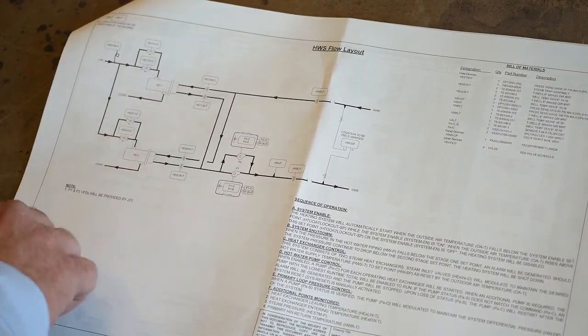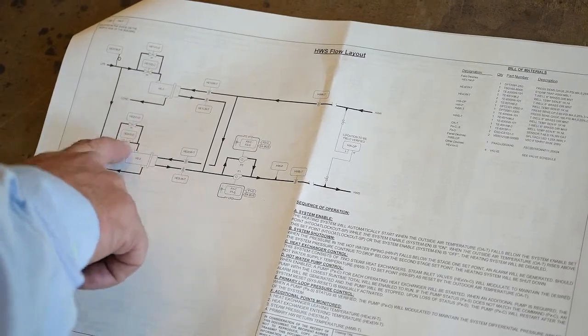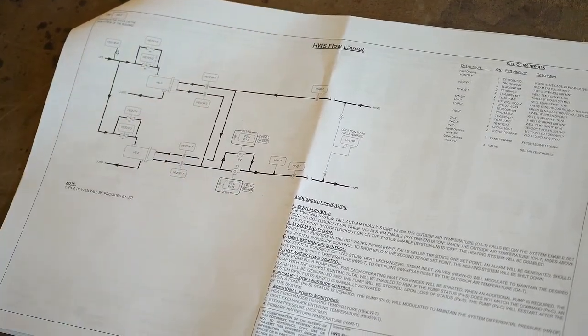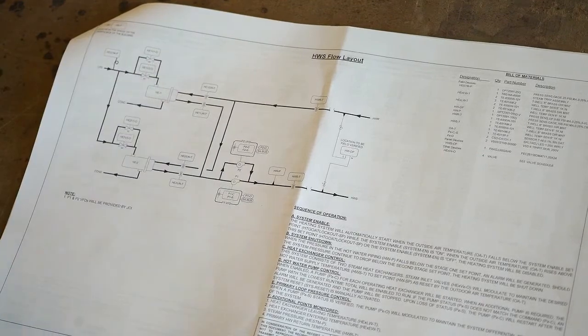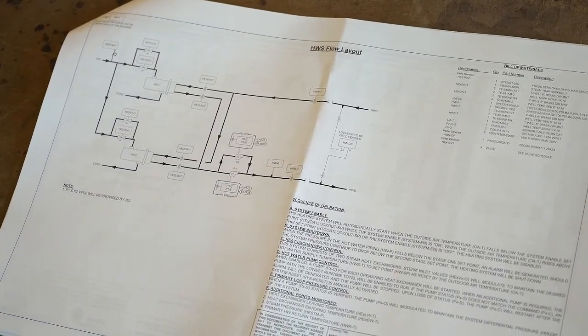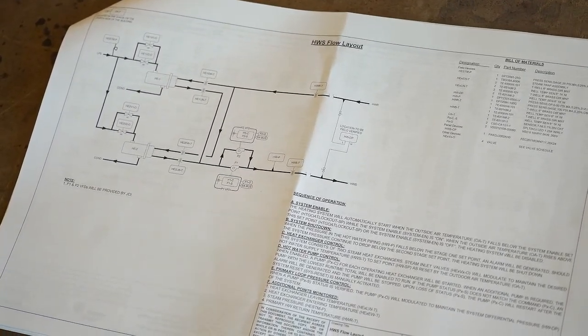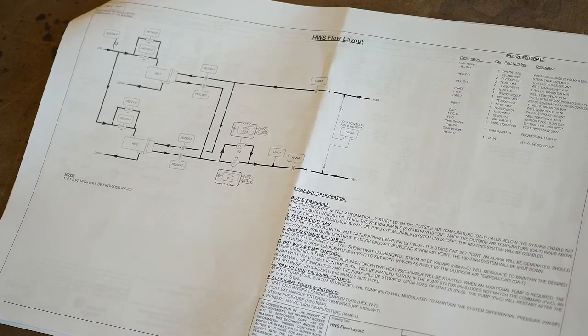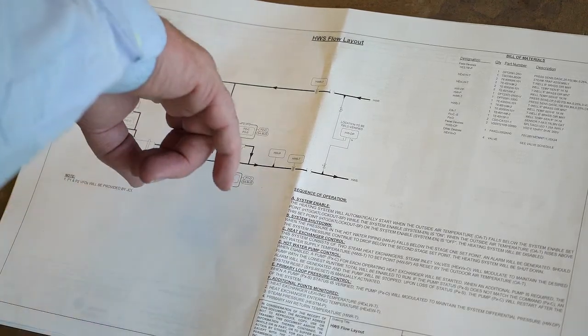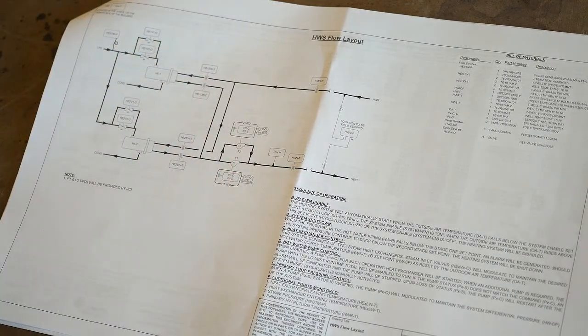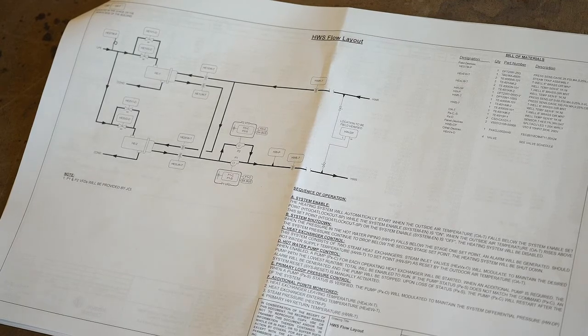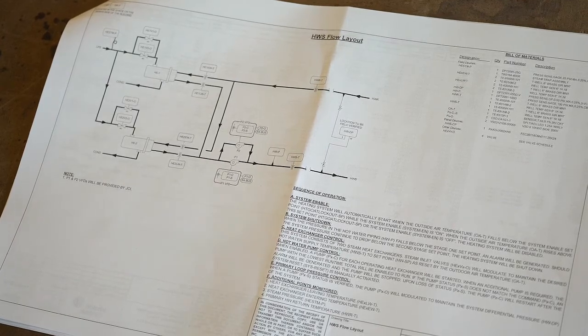So then coming into the steam heat exchangers, we have a 1/3, 2/3 valve to each heat exchanger. You guys are probably familiar with the 1/3, 2/3. The 1/3 valve just goes at low flows when there's not much demand on the building. In the winter, when it gets colder out and you get more demand, then it starts modulating that 2/3 valve open also, in order to get enough steam to heat up this water to the 140 set point. Okay. And we're maintaining a specific set point. We're not resetting based on outside air temperature.